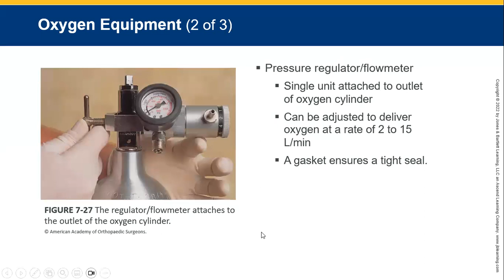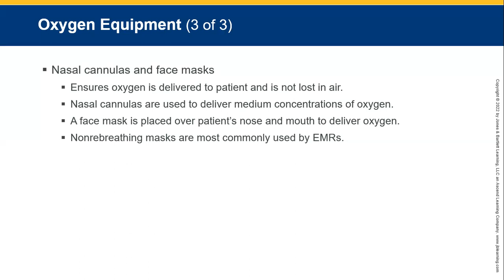Second, the type of device used. Remember, some masks can only go up to a certain percentage because they have a constriction or a baffle in there, which only allows so much oxygen to flow through the mask. Thinking of a Venturi mask, a pink one would be about 40%, 8 liters per minute. A yellow one, 4 liters per minute, 28% oxygen. And then your bag valve mask or your non-rebreather mask would give you about 90%. The third is the seal on the patient's face. The tighter the seal, the higher the percentage of oxygen that is delivered through that device.